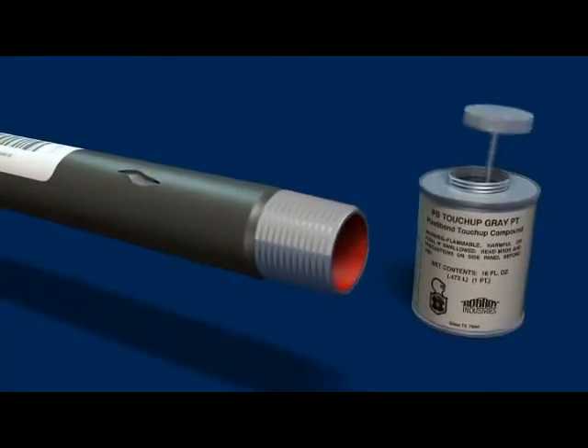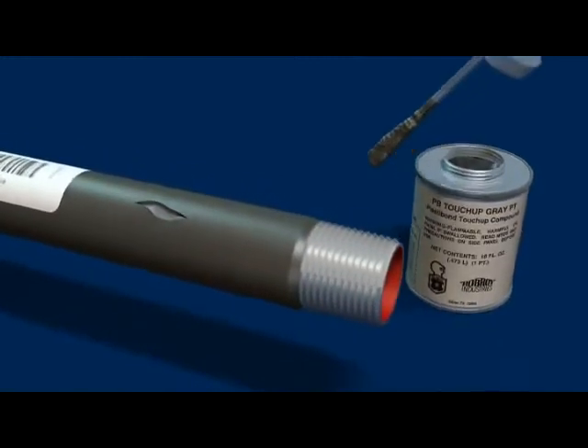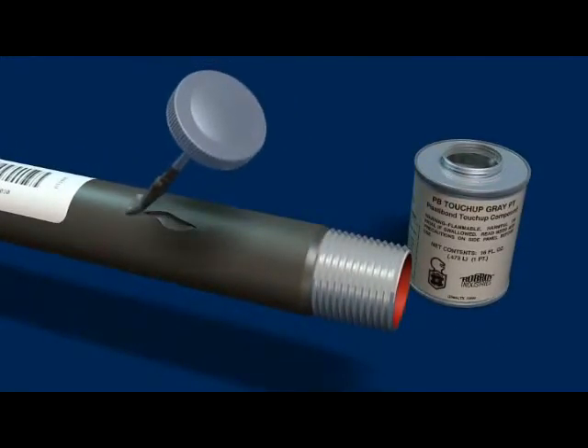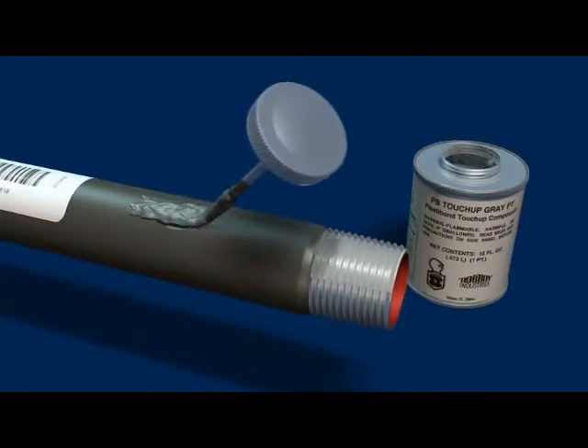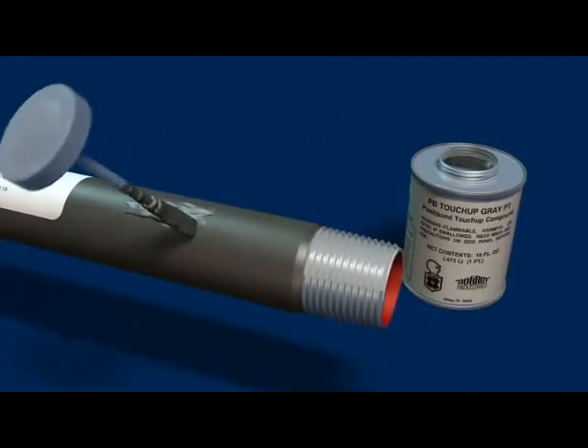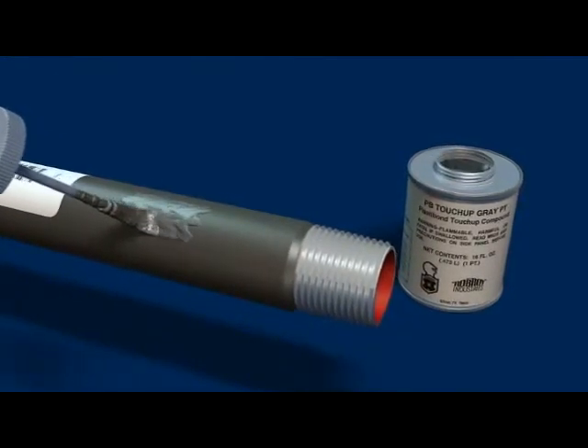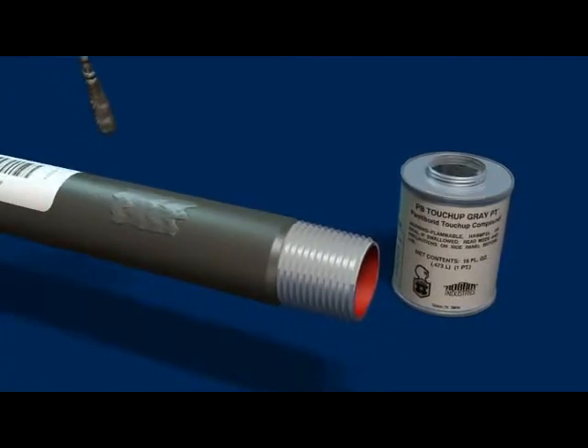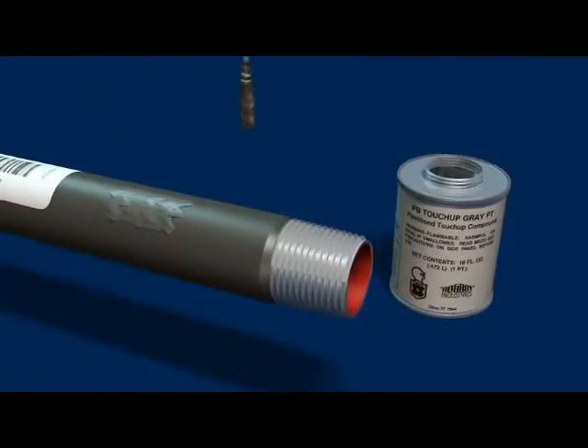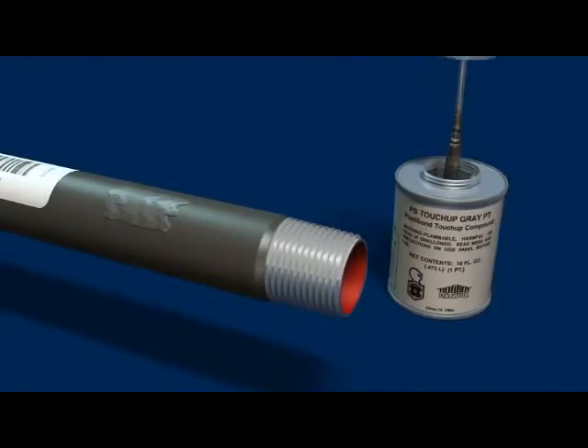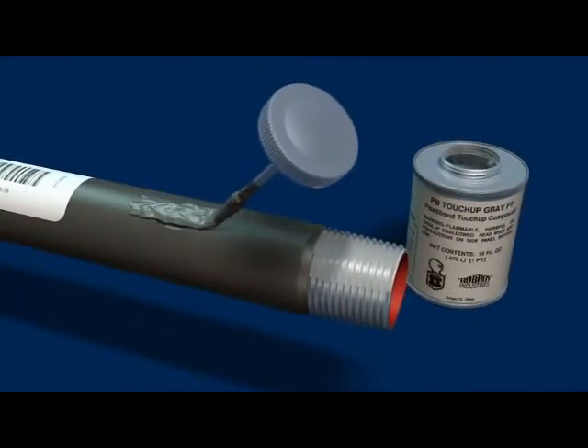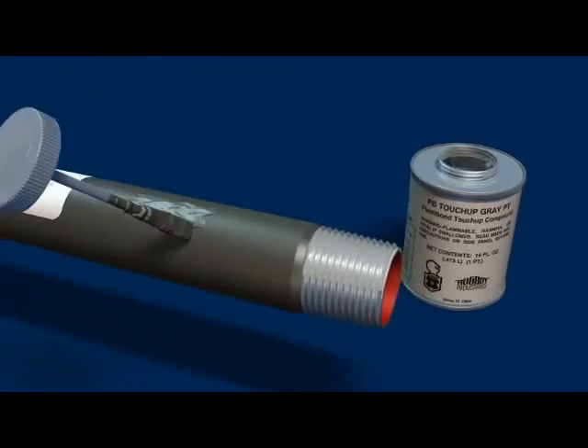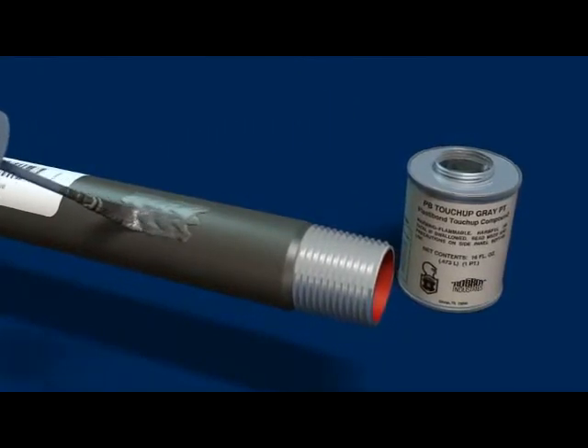PlastiBond touch-up compound is used to repair nicks, cuts and abrasions to the outer surface of PlastiBond coated conduit. Apply the exterior touch-up compound liberally over damaged areas. Because this material will not adhere to bare metal, it is advisable to overlap existing PVC coating.